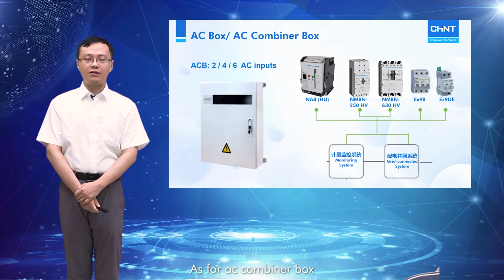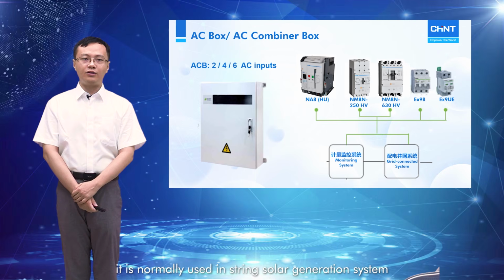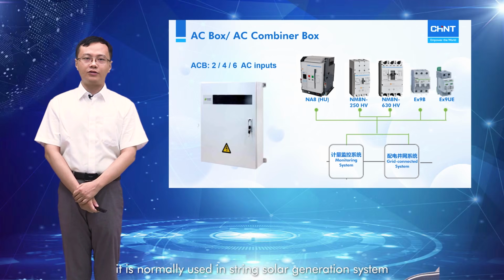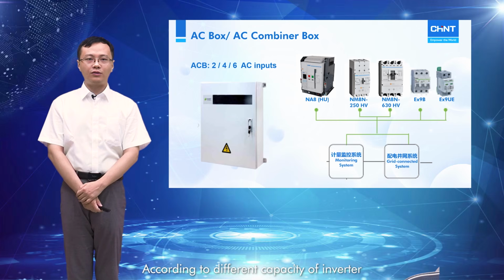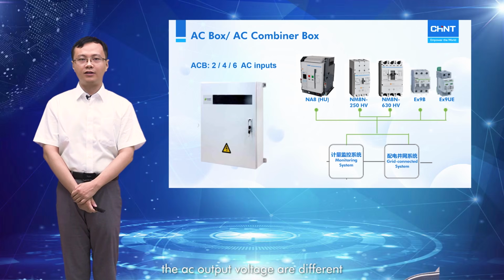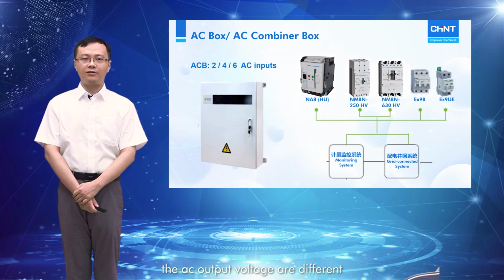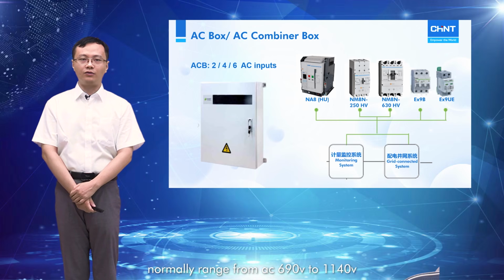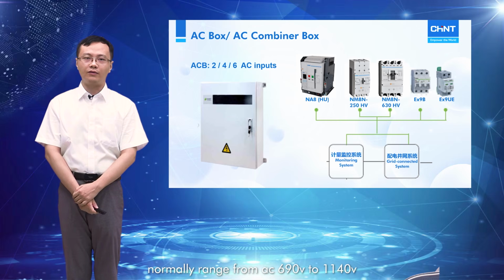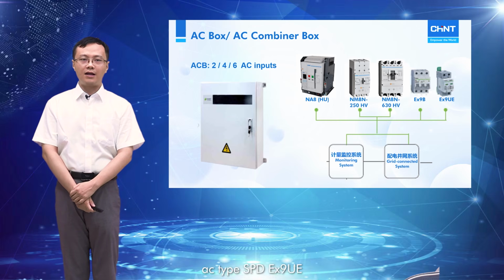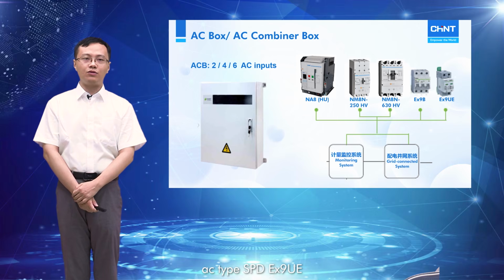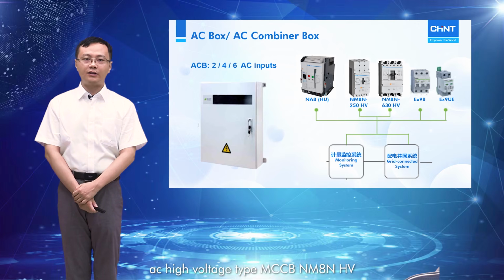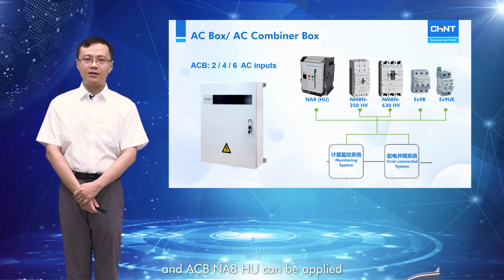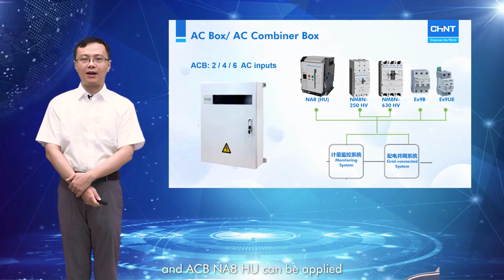As for the AC combiner box, it is normally used in a string type solar generation system. According to different capacity of the inverter, the AC output voltage is different, normally ranging from AC 690 volts to 1140 volts. In this case, AC type SPD EX9UE, AC high voltage type MCCB NM8NHV, and ACB NA8HU can be applied.